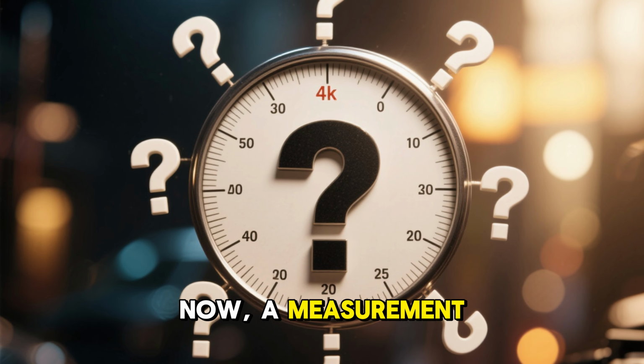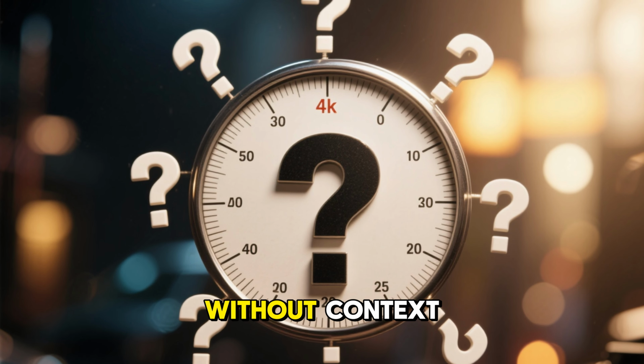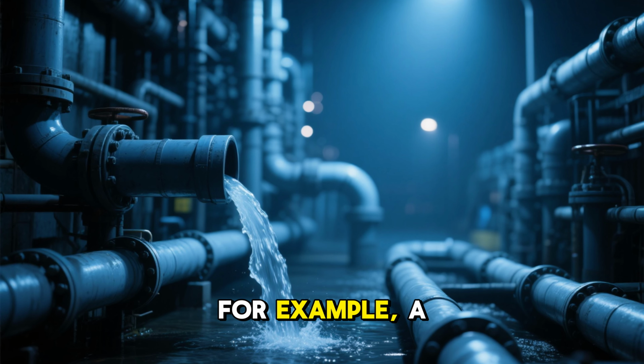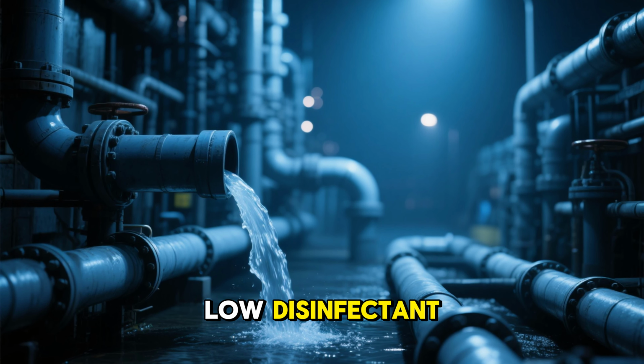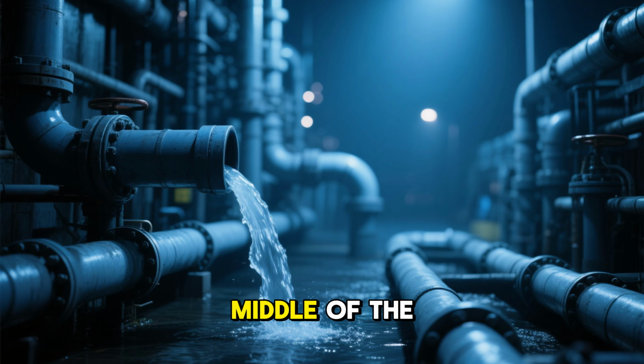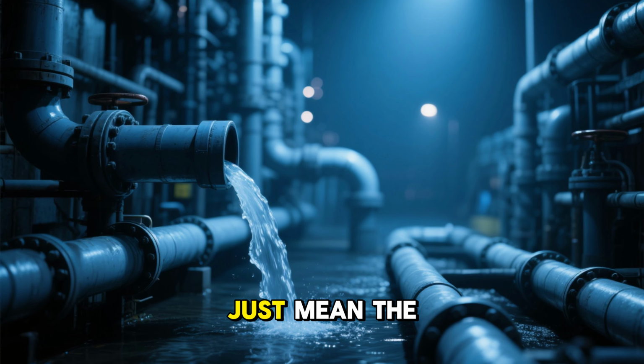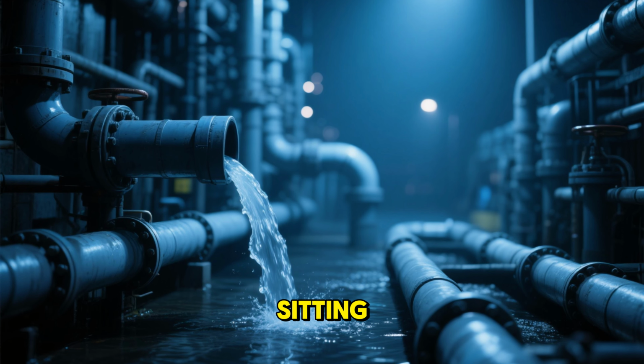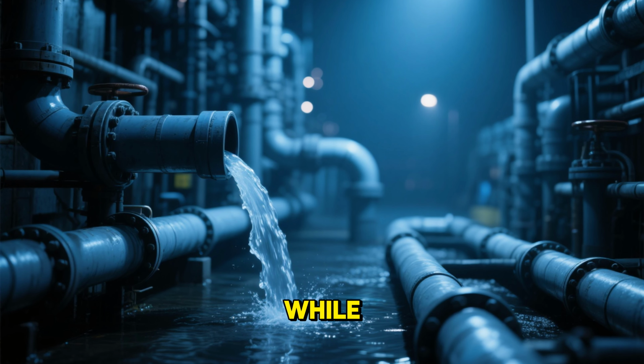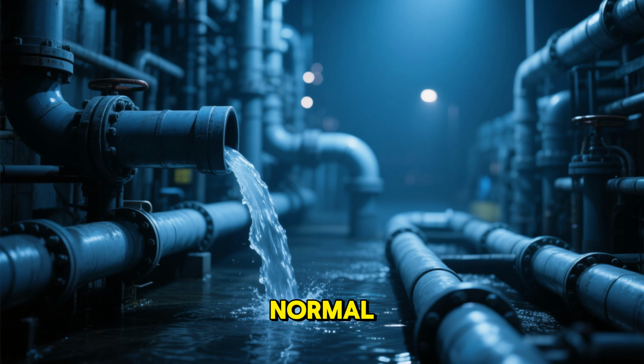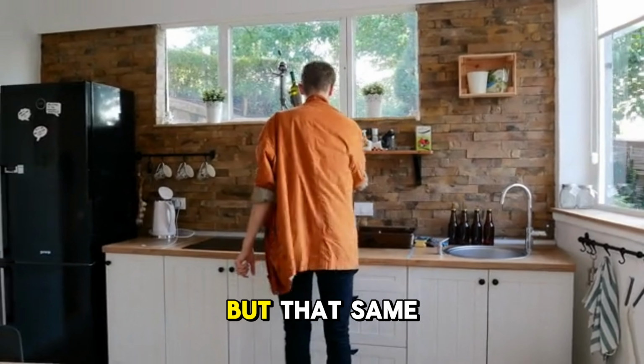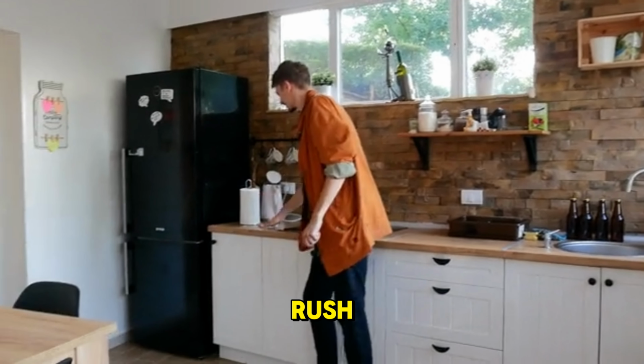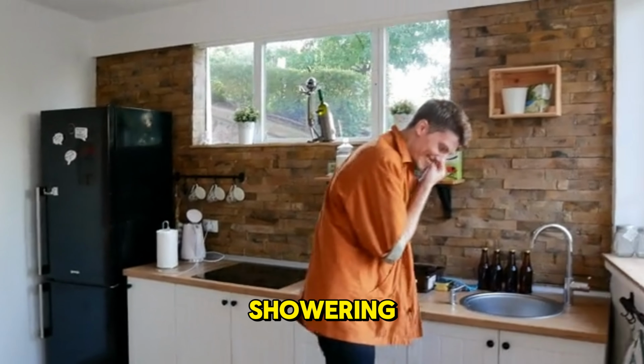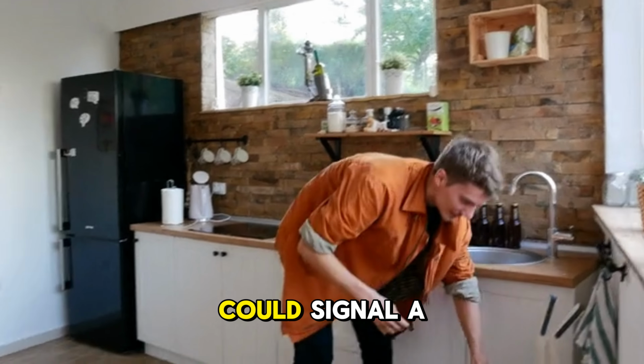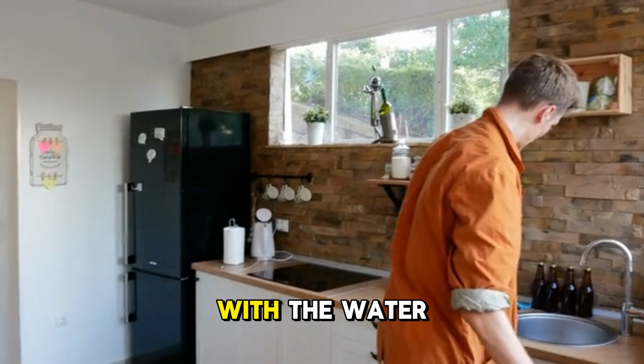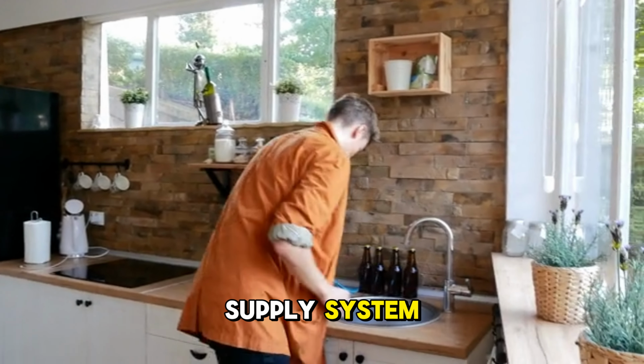Now, a measurement is pretty meaningless without context. For example, a low disinfectant level in your pipes in the middle of the night might just mean the water has been sitting still for a while, which is totally normal. But that same low reading during the morning rush, when everyone is showering and making coffee, could signal a real problem with the water supply system.